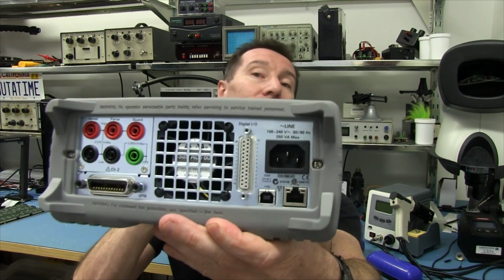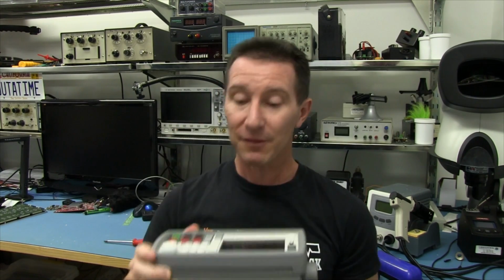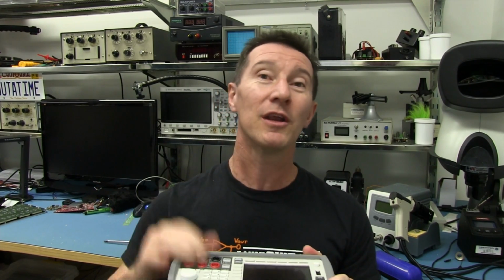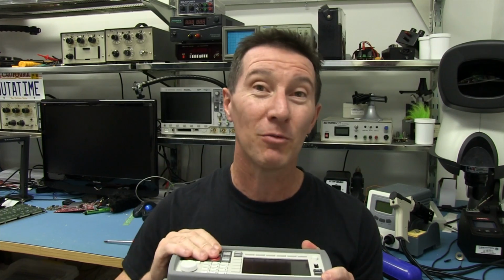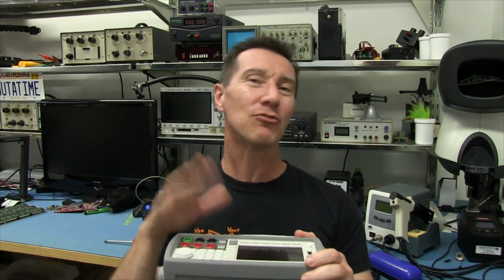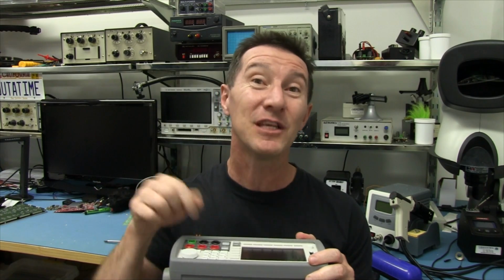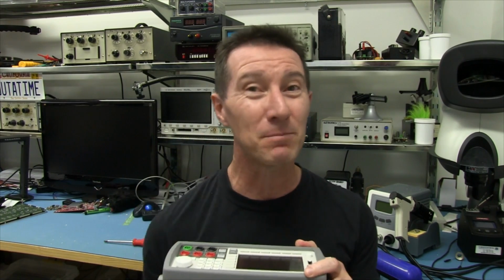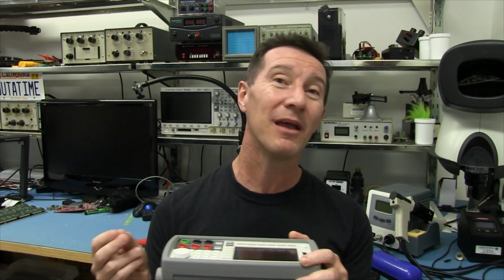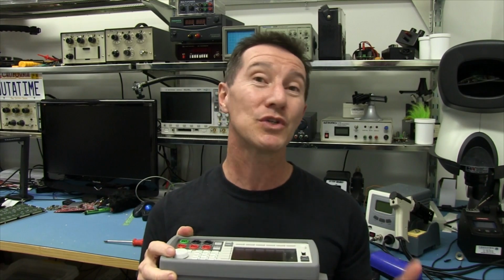So hey, maybe we can go as far as we want. So there you go, this is a dual channel unit. This model is the B2912A, comes in several models, this is the highest end unit. It's a dual channel one, so it's got the second channel on the back there. Dual channels is handy because you can do stuff you can't do on a single channel unit. It's got 4-terminal measurement, all sorts of stuff, a fancy graphical LCD display, and this one can go down to 10 femtoamps resolution - anywhere from 10 femtoamps up to a couple of amps, sourcing and measuring.